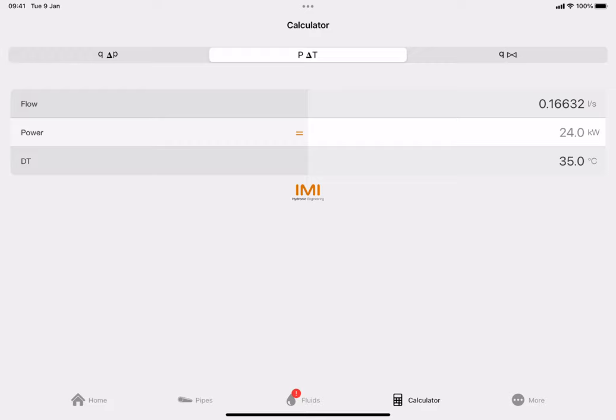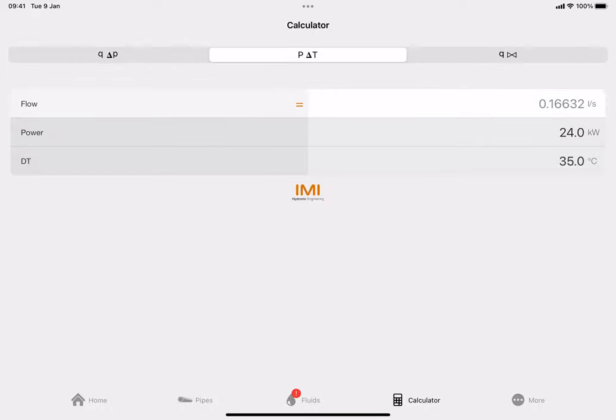The bits in gray that you can see grayed out on both sides - you've got flow, DT, and the 0.16 liters per second and 35 degree centigrade in the bottom right-hand corner - those can all be changed. If you want the answer for pipe sizing, we would want the equals to be in front of the flow. Click on 'flow' like that and then you get the equals. You can now change any of the other two parameters - click flow, power, or Delta T on the left-hand side and then change the two other figures on the right-hand side to get your calculations.